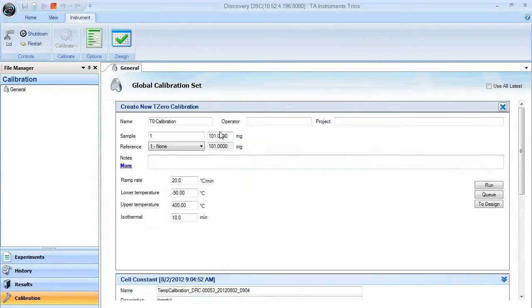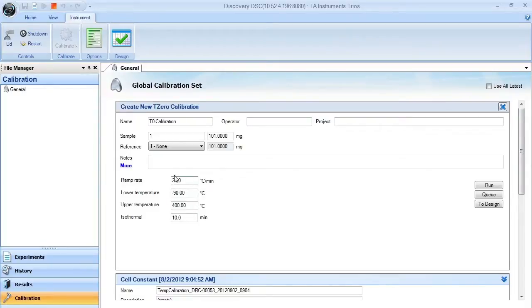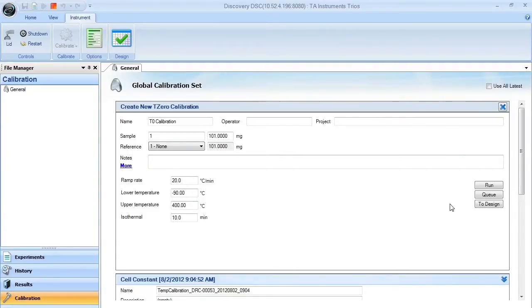When your sample sapphire and reference sapphire locations are correct, and the weights are correct, make sure that your temperature limits are correct. You do not need to enter or change the ramp rate. Leave it at 20 degrees C per minute.